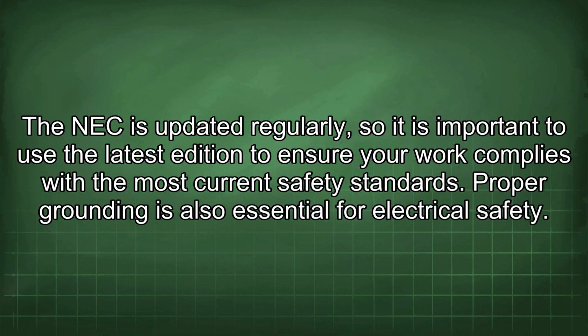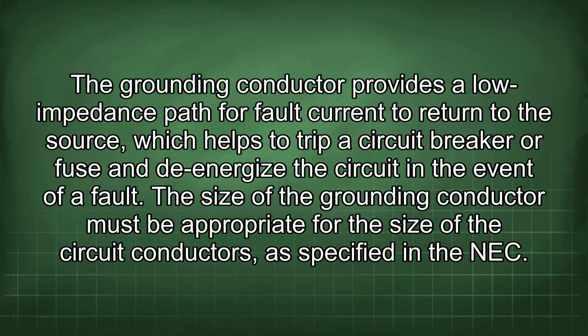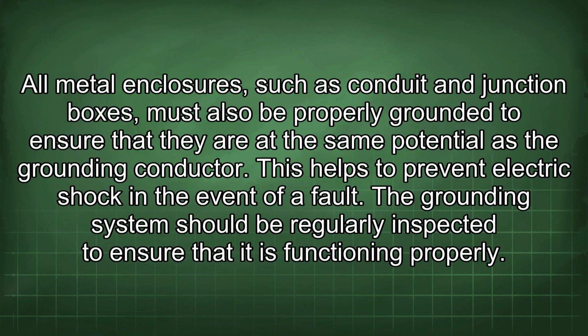Proper grounding is also essential for electrical safety. A grounding conductor provides a low impedance path for fault current to return to the source, which helps to trip a circuit breaker or fuse and to de-energize the circuit in the event of a fault. The size of the grounding conductor must be appropriate for the size of the circuit conductors, as specified in the NEC. All metal enclosures, such as conduit and junction boxes, must also be properly grounded to ensure that they are at the same potential as the grounding conductor. This helps to prevent electric shock in the event of a fault.